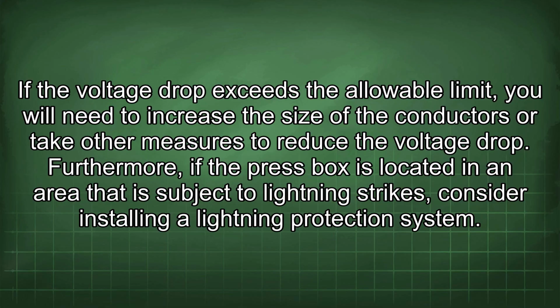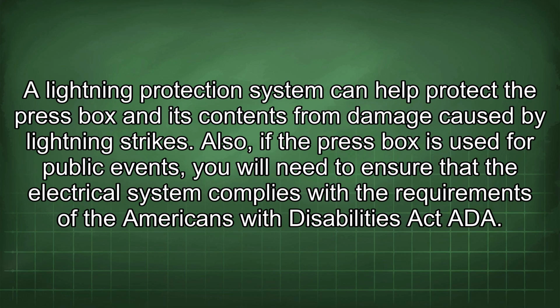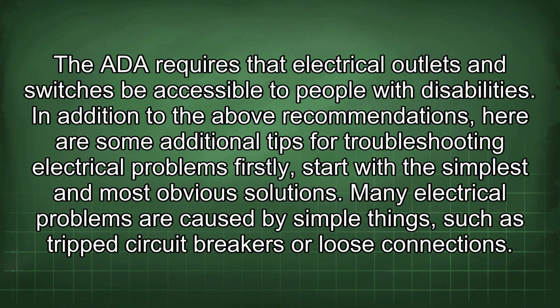Furthermore, if the press box is located in an area that is subject to lightning strikes, consider installing a lightning protection system. A lightning protection system can help protect the press box and its contents from damage caused by lightning strikes. Also, if the press box is used for public events, you will need to ensure that the electrical system complies with the requirements of the Americans with Disabilities Act (ADA). The ADA requires that electrical outlets and switches be accessible to people with disabilities.